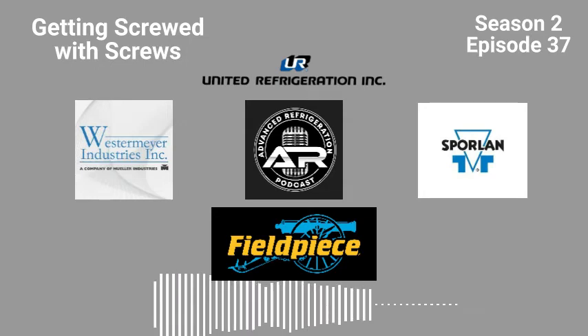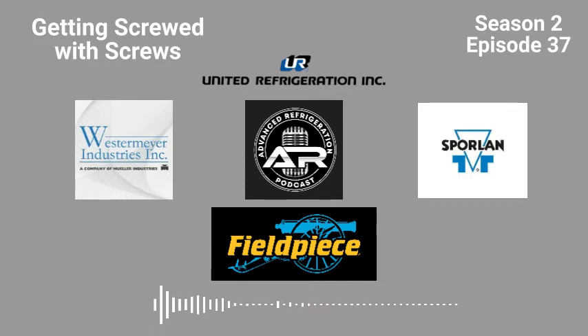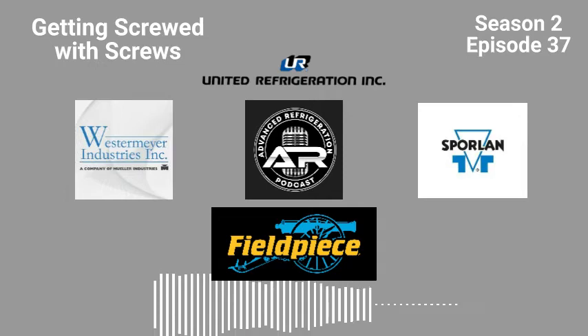So after all that mess, I go back to my startup after I'm covered in oil, and we get these compressor pucks out. There's no way to shut the discharge off, but in another month they're going to be all cut out and replaced anyway. I'm not messing with it. All the valves are getting changed, part of a rack rebuild. So we pull the pucks out.